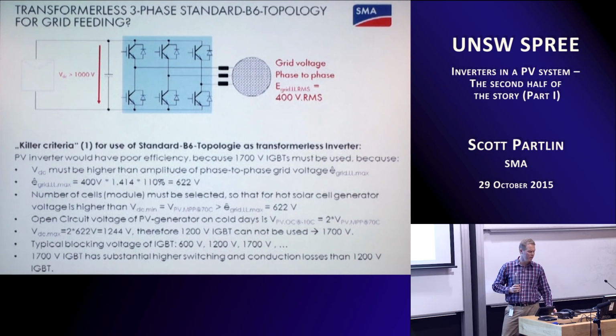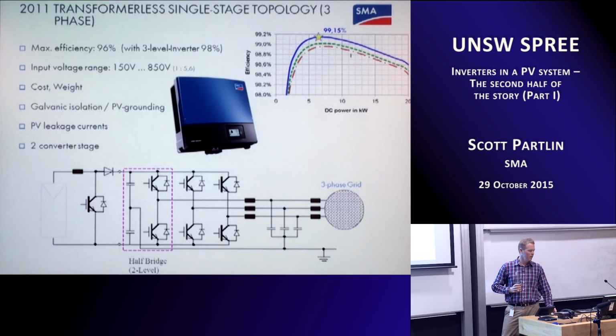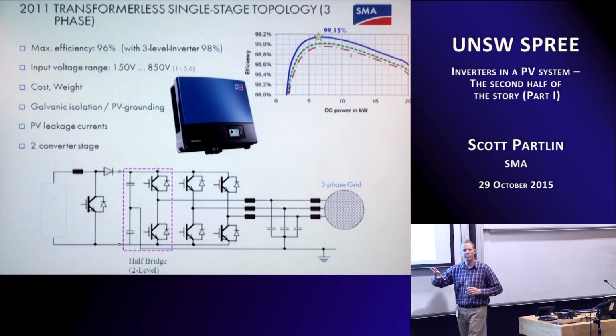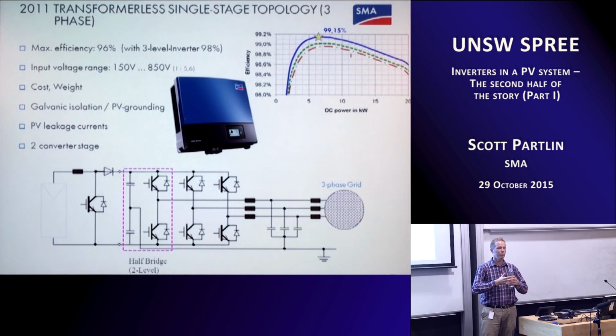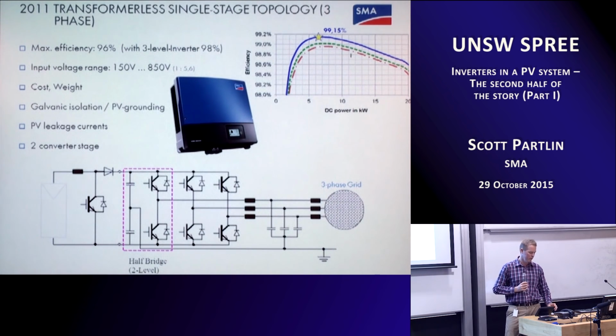So the circuit design had to change to this. As with the advent of the H5 bridge, which was able to increase the DC input window, a similar concept was then applied to the three-phase circuits that then allowed three-phase inverters like this, and I'm pretty sure these inverters might be on the roof of this building as well. It allowed inverters like this to be mass-produced, and you can see there were certain forms of this product that were manufactured that had peak efficiencies over 99%, and that's where the technology today is trending towards, across all manufacturers, always pushing towards greater than 99% efficiency.